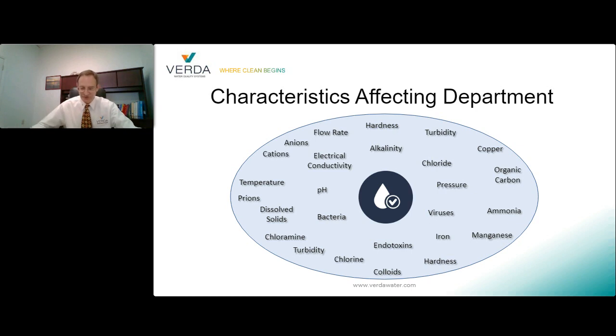It identifies 18 different parameters to monitor and test on the utility water, on the critical water, and the steam used in the SPS. And I could spend much of my remaining time going through each and every one of these parameters and how they affect what you're doing, the performance of the reprocessing equipment, the cleaning, disinfecting and sterilization of instruments, and what levels are acceptable. So does this mean we all need to go back to school and become chemists? No, but a basic understanding will help you run a successful SPS. And I encourage all of you to read the AAMI guideline and the new standard when it's released. Each document is less than 80 pages. It's worth your investment.